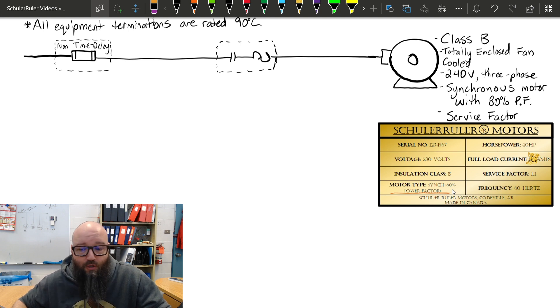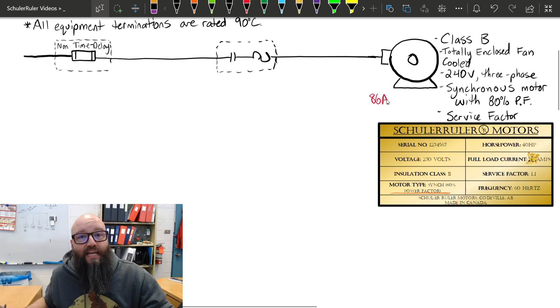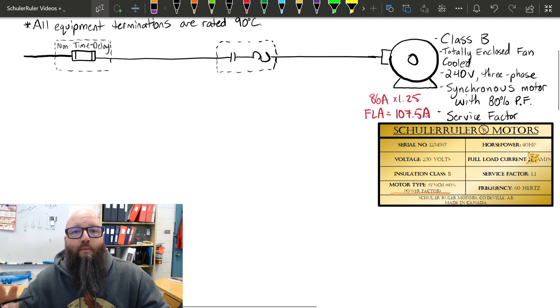Cross-referencing voltage and horsepower, we find out that normally with this unity power factor we'd be looking at 86 amps as an FLA. But because it's an 80% power factor, we're going to use that times 1.25 to determine what our actual FLA is that we're going to use in this question. Fire that into the calculator. We find out our FLA in this example is going to be 107.5 amps. That's our magic number for our motor calculation.